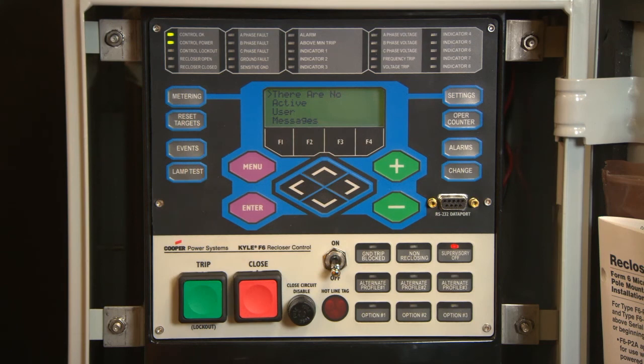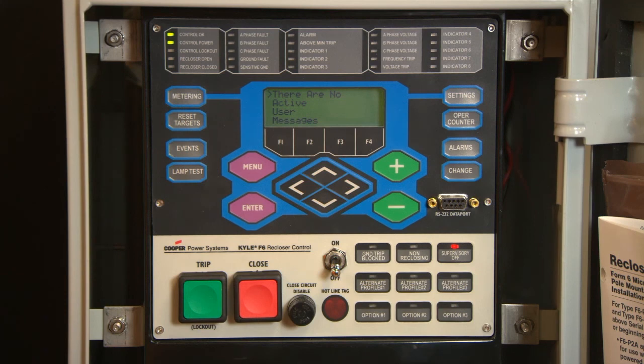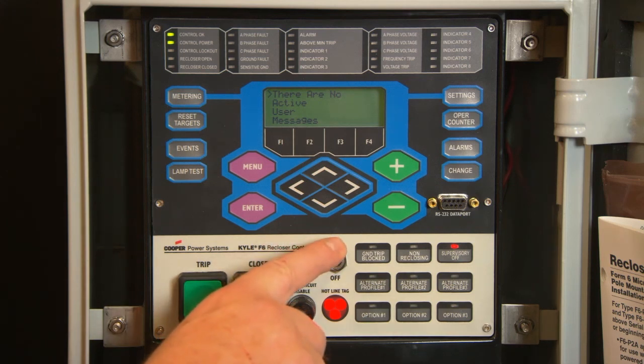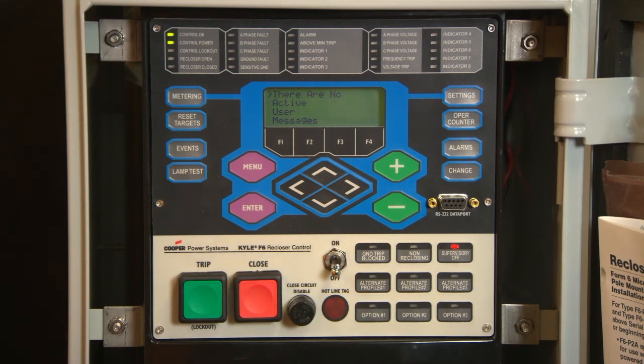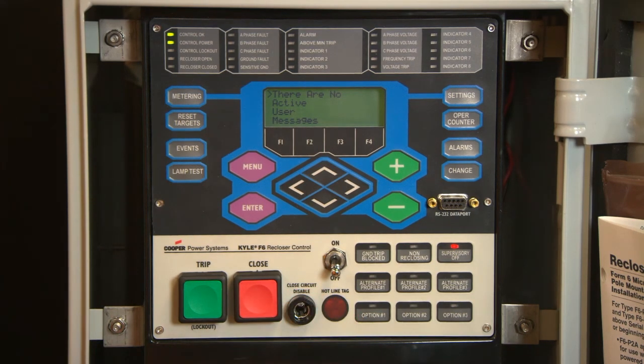Hotline tag, hold off. This is a toggle switch in the center of the control. Flipping this switch in the up position will activate the hotline tag as indicated by the LEDs. This will give you one fast operation until lockout. Under this condition, you cannot close the unit back in if it trips out. You must first remove the hotline tag. If you wish to disable the close circuit, there is a fuse that can be removed. This is typically only used for testing procedures.